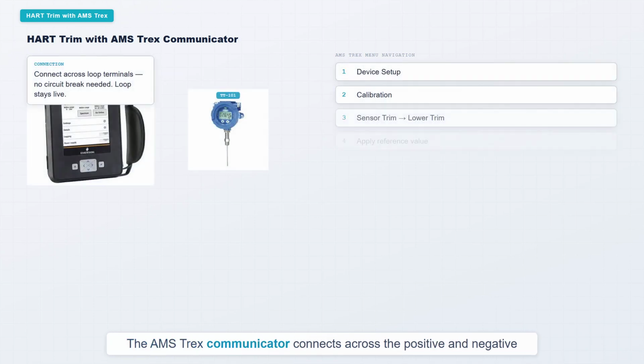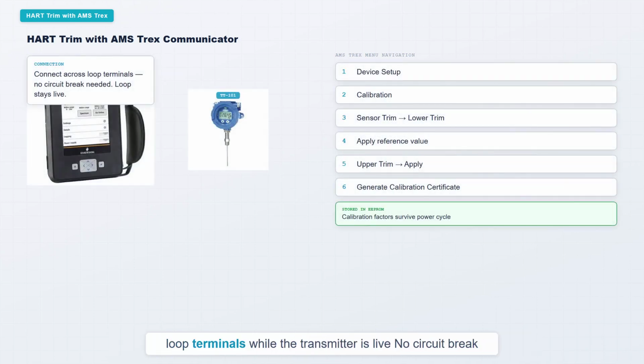The AMS Trex communicator connects across the positive and negative loop terminals while the transmitter is live. No circuit break needed. From the home screen, navigate to Device Setup, then Calibration, then Sensor Trim. The communicator walks you through lower and upper trim steps. You enter the decade box resistance, command the trim, and the AMS writes the new calibration factors into the transmitter EEPROM. These factors survive a power cycle. When the trim is complete, generate the calibration certificate directly from the AMS. Record the as found and as left values. This documentation is your proof of calibration for the next audit.